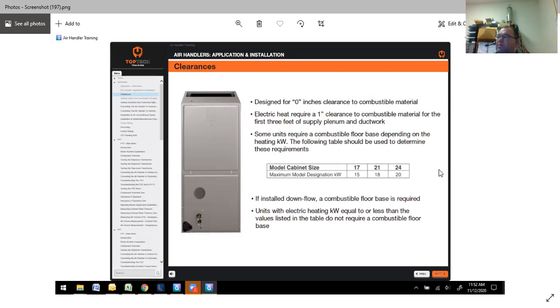Clearances: they're designed for 0 inches of clearance to combustible materials. Electric heat requires 1 inch clearance to combustible material for the first 3 feet of the supply plenum and ductwork. Some units require a combustible floor base depending on the heating kilowatts. The following table shows where these fall on the requirements. If installed in a downflow position, a combustible floor base, a small riser box, is required. Units with electrical heating kilowatts equal to or less than the values listed in the table do not require a combustible base.